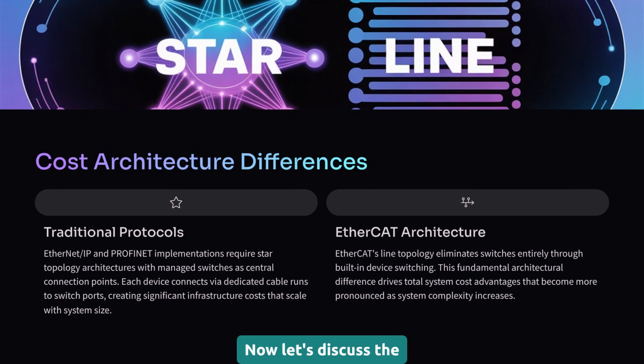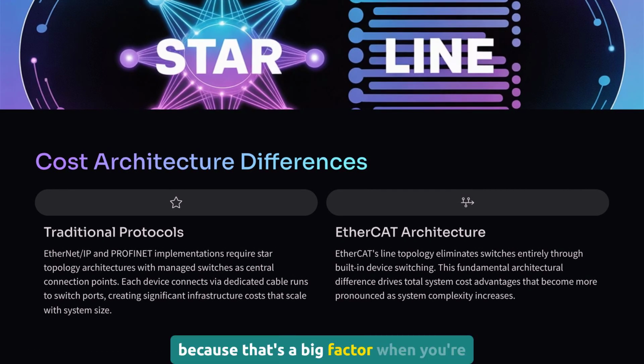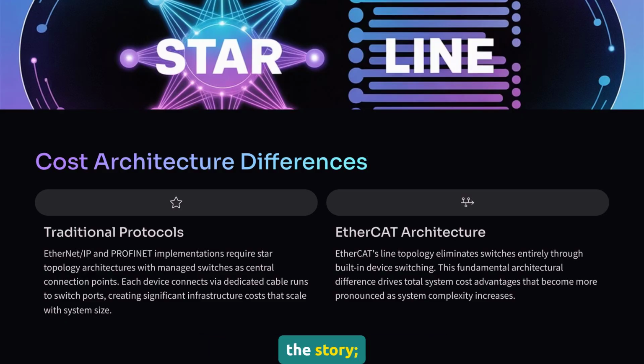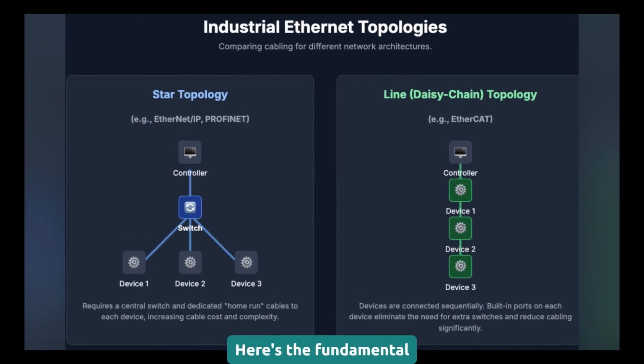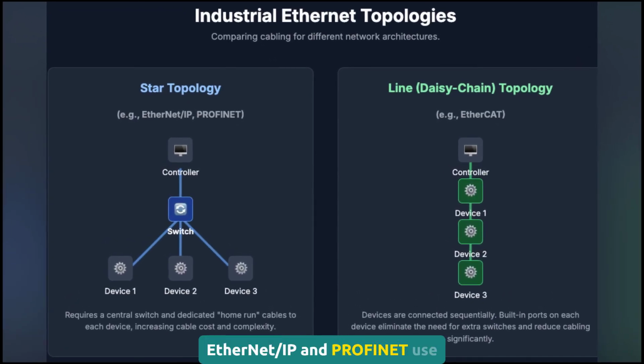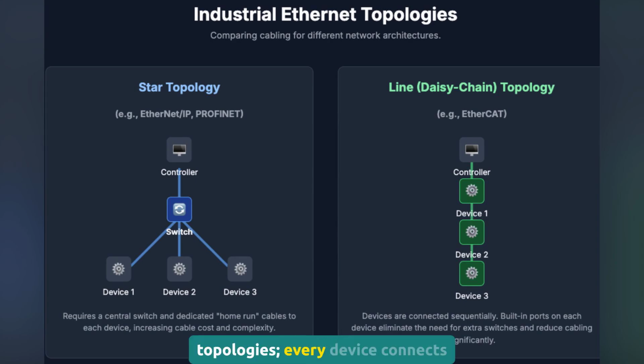Now let's discuss the economics, because that's a big factor when you're specifying a system. After installing dozens of networks, I can tell you that device cost is just part of the story. Infrastructure and installation labor often drive the total project cost. Here's the fundamental difference. Ethernet IP and PROFINET use star topologies. Every device connects back to a managed switch. EtherCAT uses a line topology. Devices daisy chain from one to the next. This topology difference drives most of the cost variance.